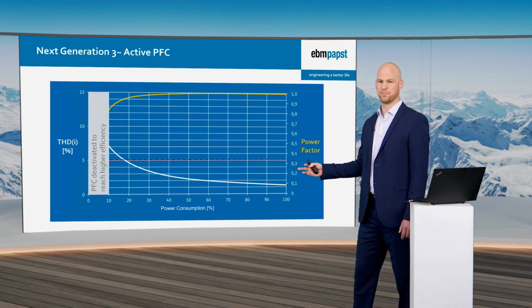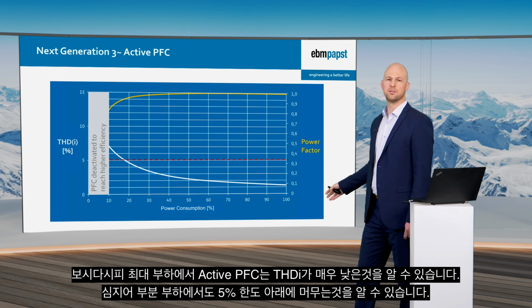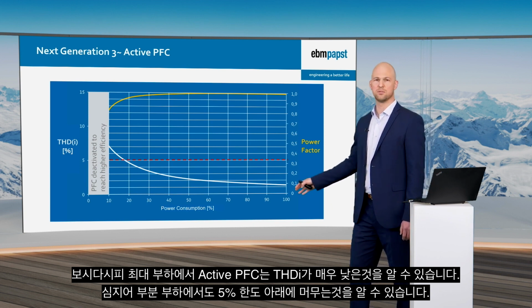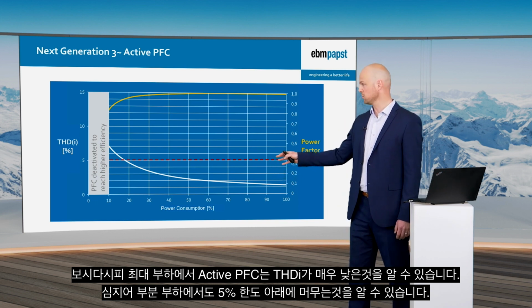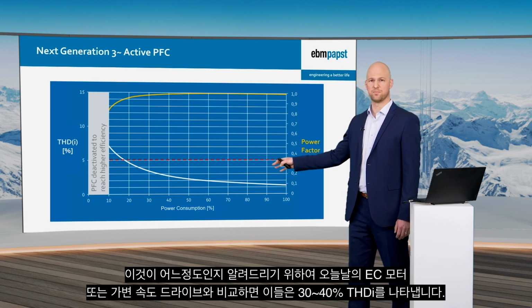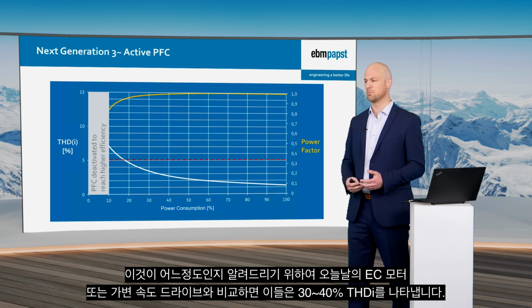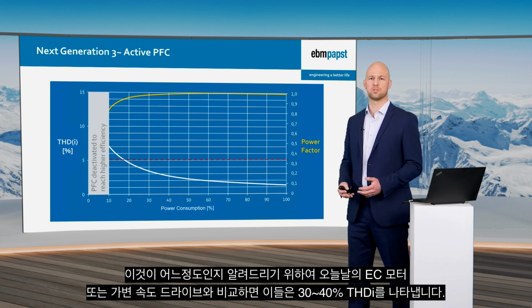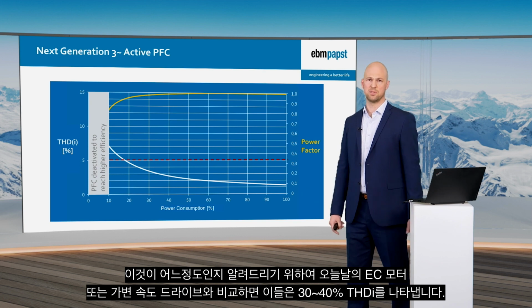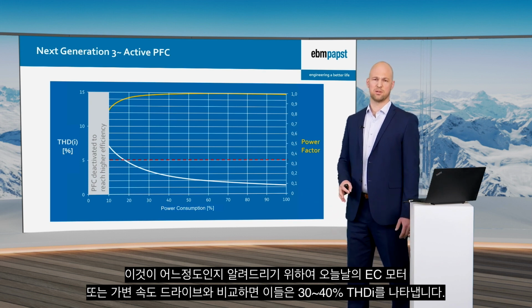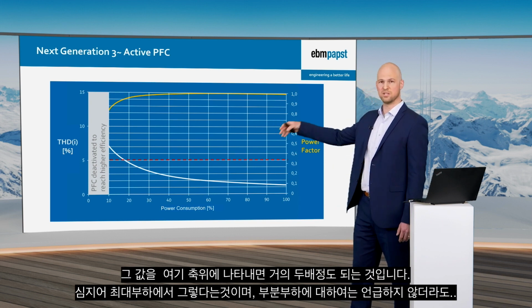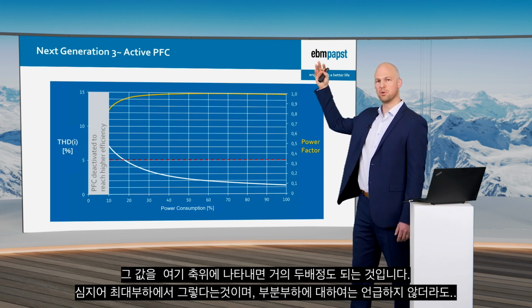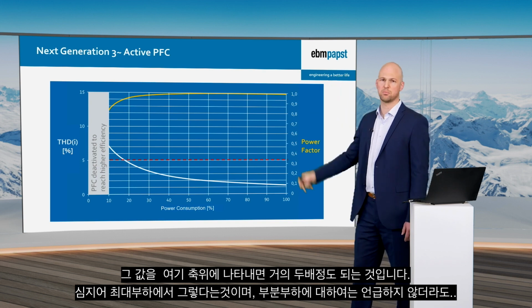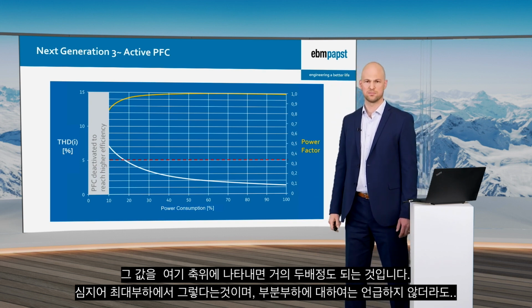As you can see, at full load the Active PFC has a very low THDI, and even in the partial load range it stays below the 5% margin. Just to give you a feeling what this means, compare it with today's EC motors or market standard variable speed drives: they range around 30 to 40% THDI. So on this axis you would have to double it, and the values would still be above that at full speed, not even talking about partial load, where it would be even worse.